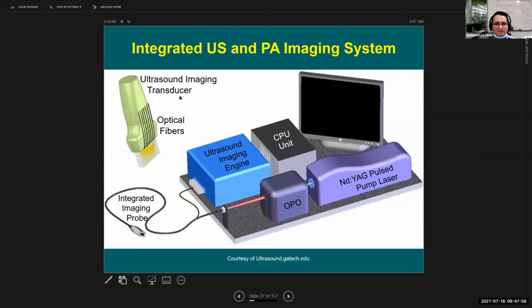All right, so a typical combined or integrated ultrasound and photoacoustic imaging setup: you basically have an ultrasound engine, mostly an acquisition system, or transmit and acquisition ultrasound system. You put a pulse laser next to it. Most of the time, the lasers we use for photoacoustic imaging consist of a pump and an OPO. The OPO is basically an oscillating crystal that is able to provide or generate laser output at different wavelengths.